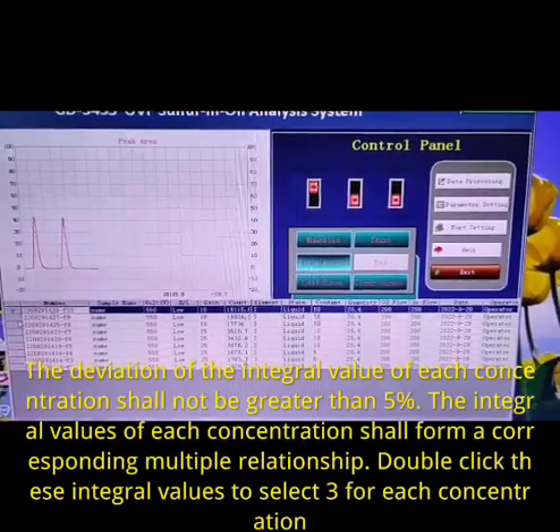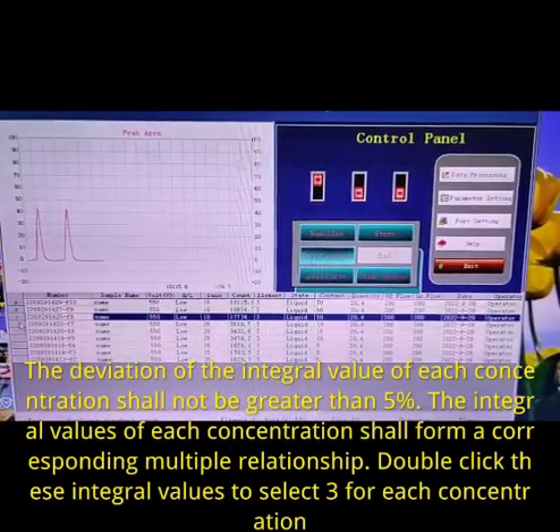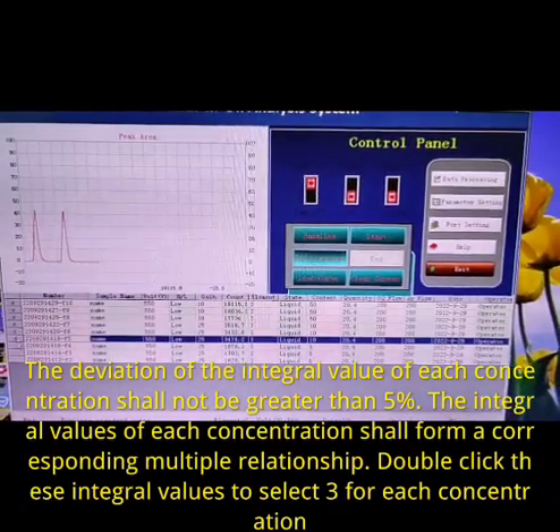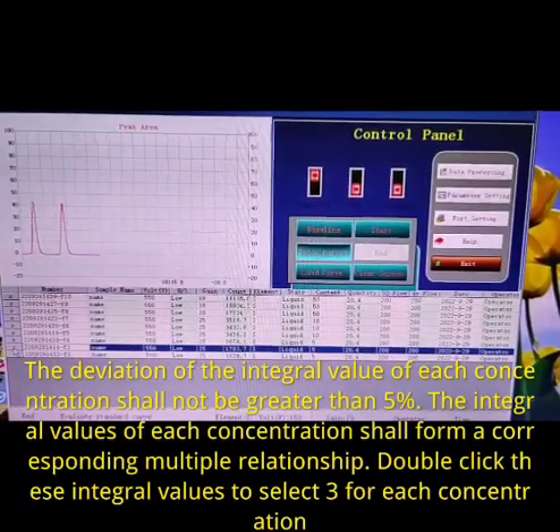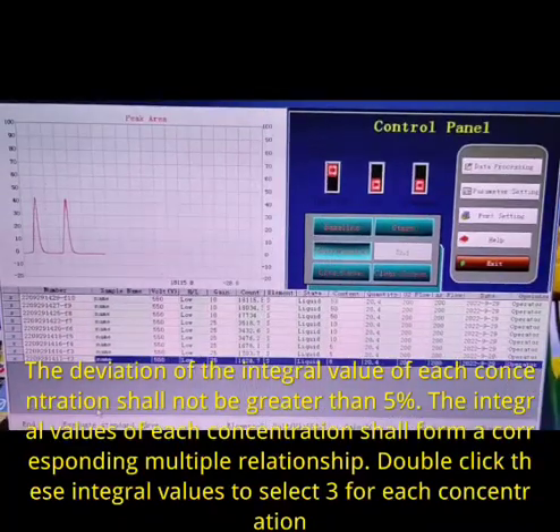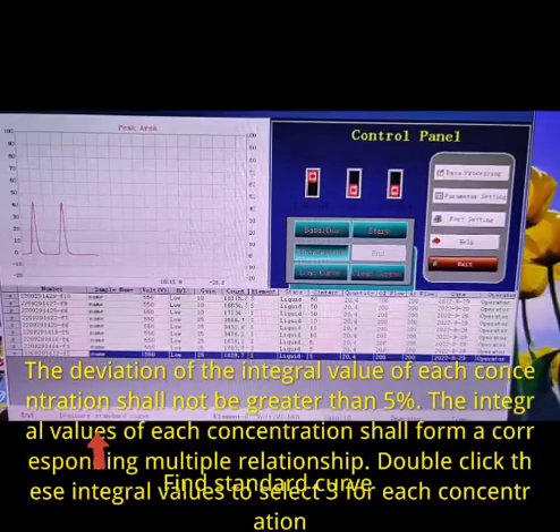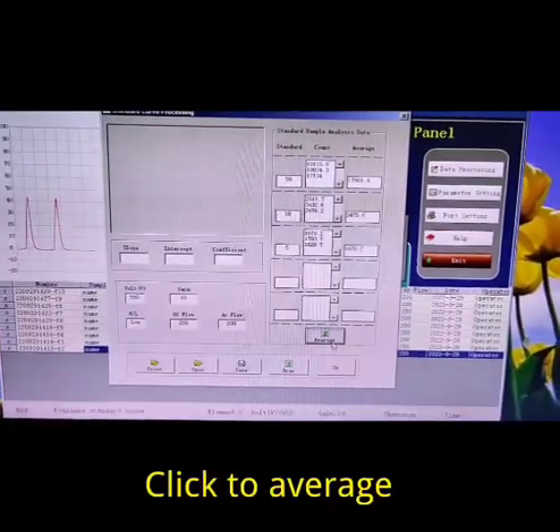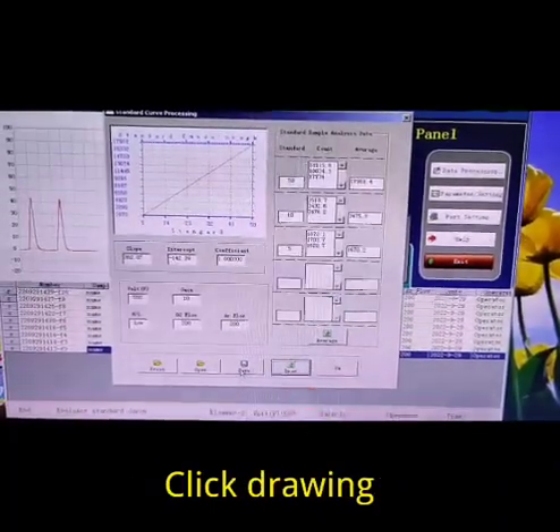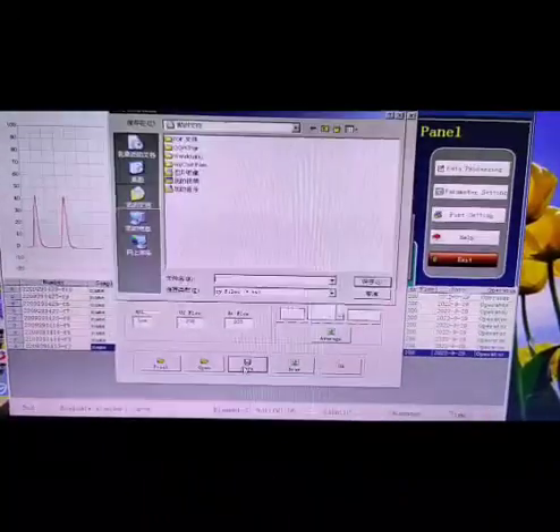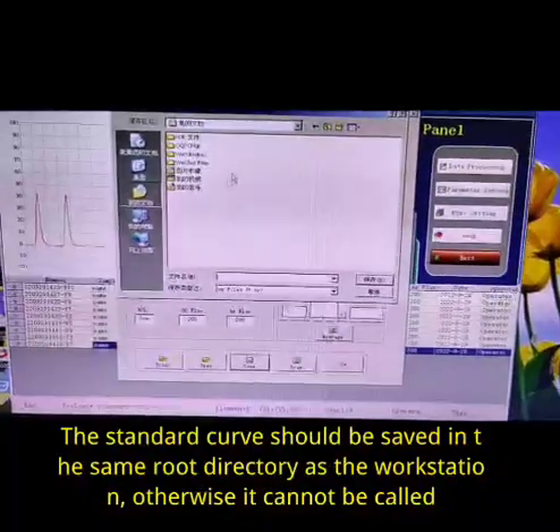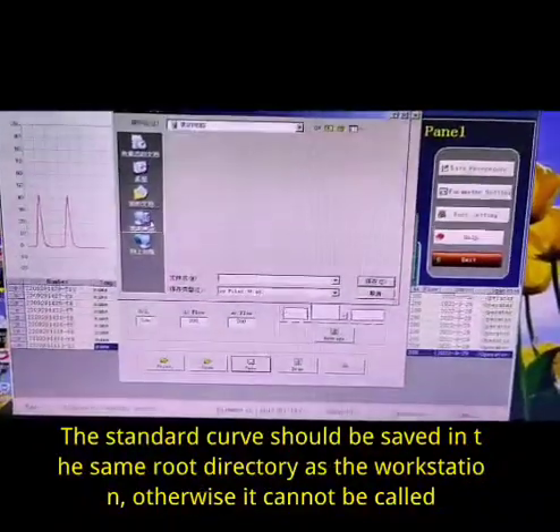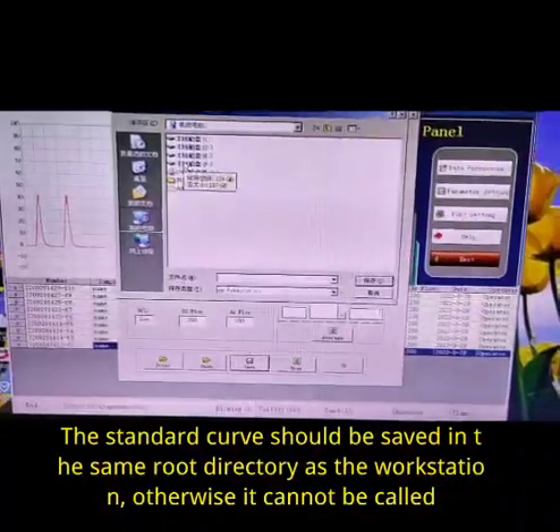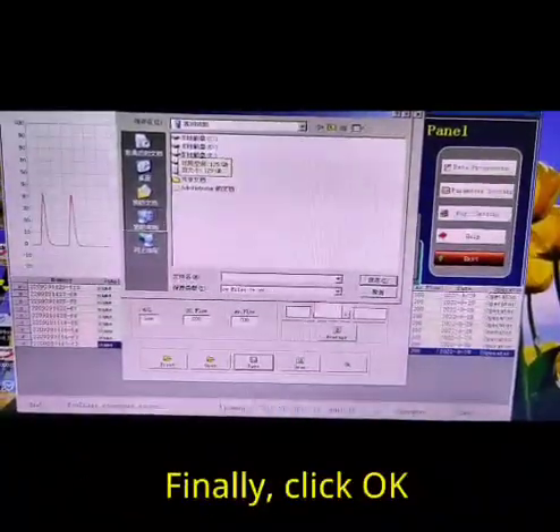The deviation of the integral value of each concentration shall not be greater than 5%. The integral values of each concentration shall form a corresponding multiple relationship. Double-click these integral values to select 3 for each concentration. Find standard curve. Click to average. Click Drawing. Click Save. The standard curve should be saved in the same root directory as the workstation, otherwise it cannot be called. Finally, click OK.